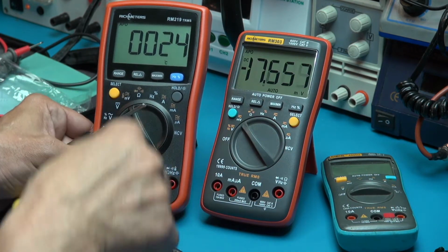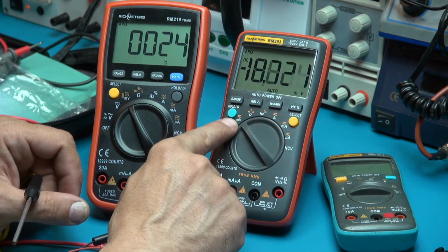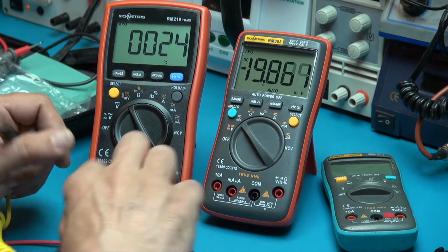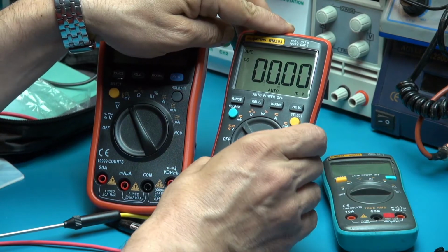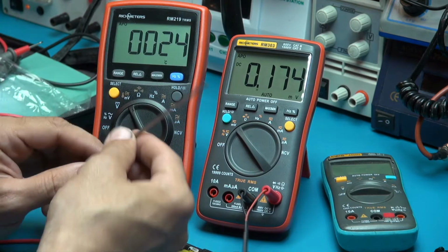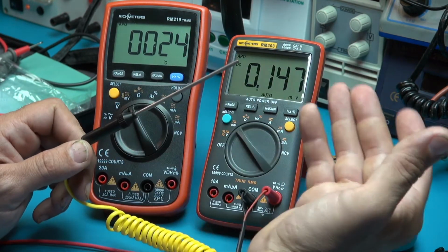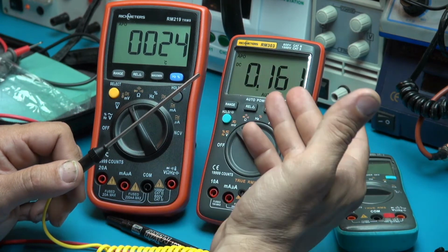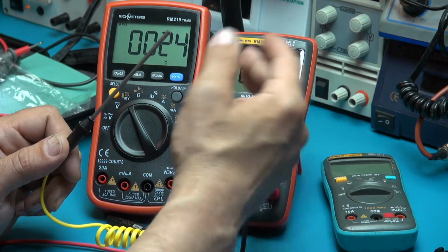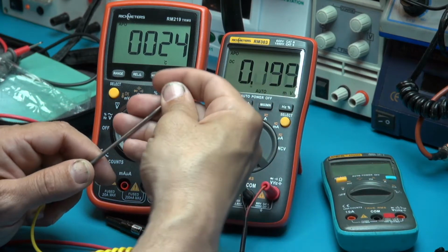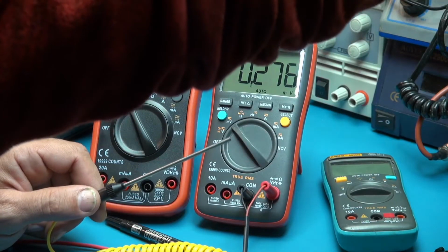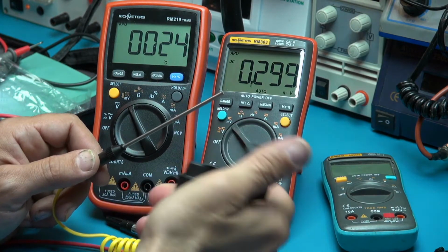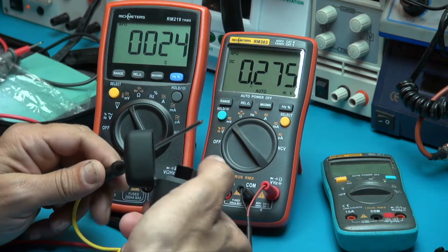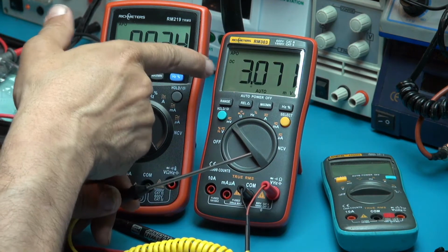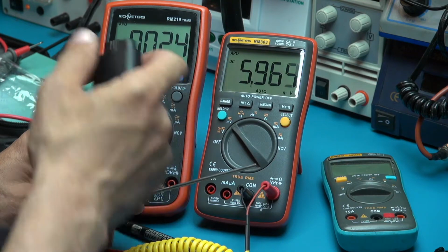So on this one you will not have the temperature readings, but you only have millivolt readings. Also, if you have special requests, you can read the temperature according to the millivolts you read, because a thermocouple is able to provide a millivolt voltage to your operators, which can give you an idea about the temperature of the thermocouple. So for instance, this is a lighter. You can see the millivolt reading. If I heat up, you can see the millivolts rising a lot because of the very fast heating of this heater.